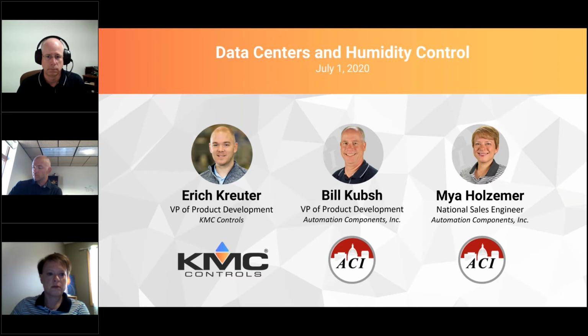Yeah, that leads me into my next topic, which is what happens with software. Many buildings have automation systems for their occupants, but what does a data center need? I was thinking along those same lines, because a lot of those BMS systems, even inside data centers, require integration. It's not necessarily BACnet and Modbus, like rooftops and heat pumps, but we may be integrating IT equipment, like servers, talking SNMP.